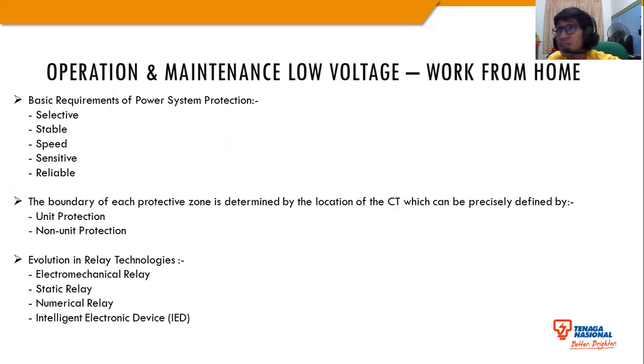The unit protection is known as main protection and has a defined area of coverage with fast operating time. Examples are feeder current differential, restricted earth fault, and transformer biased differential. Then there is non-unit protection, known as backup protection, with wider area of coverage and slower operating time, like overcurrent, earth fault and standby earth fault.